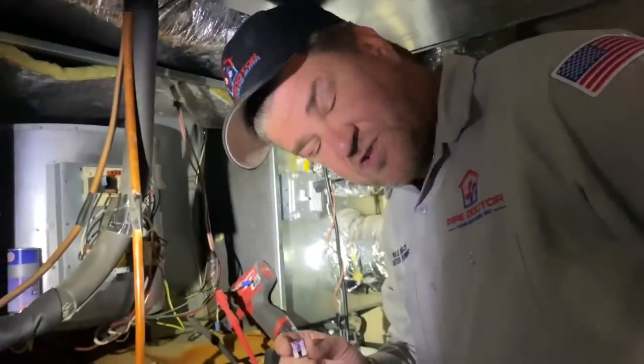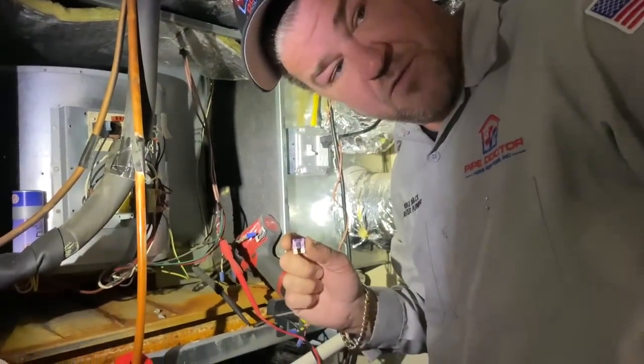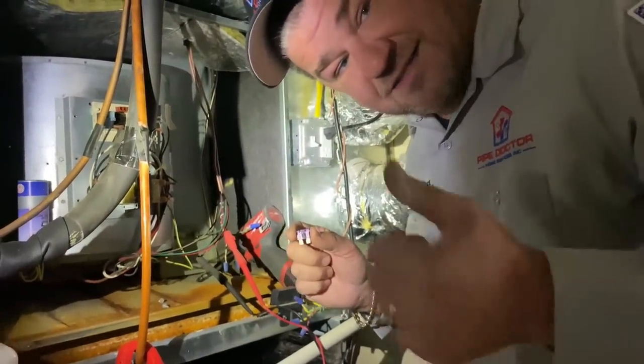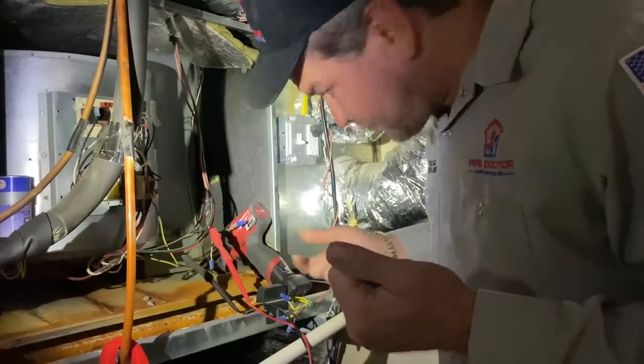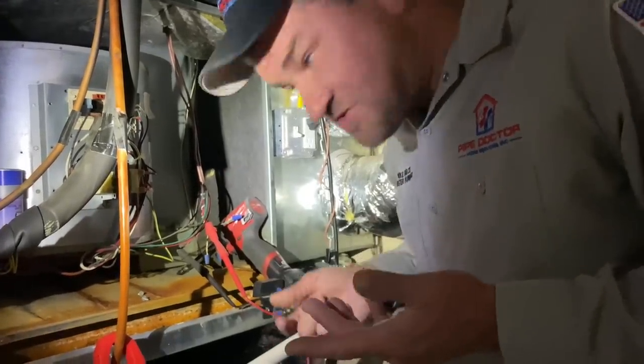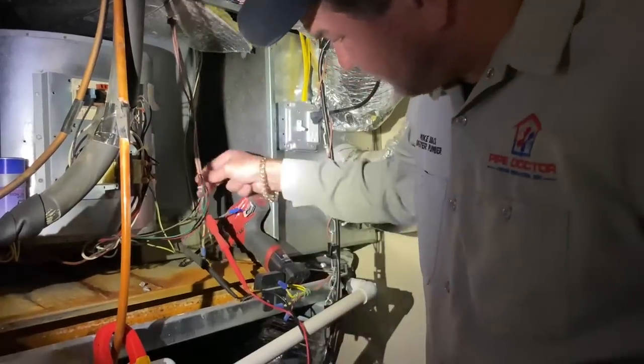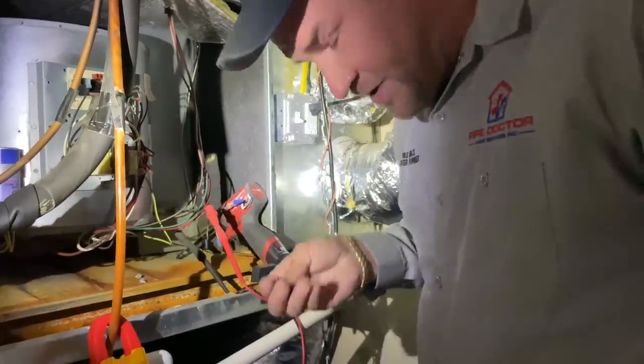So what could cause a blown fuse? Well, a short in the low voltage control wiring. It could be a contactor outside. We could have a short when someone maybe played with a thermostat, or maybe there's frayed wires touching each other. So we're going to get another fuse.